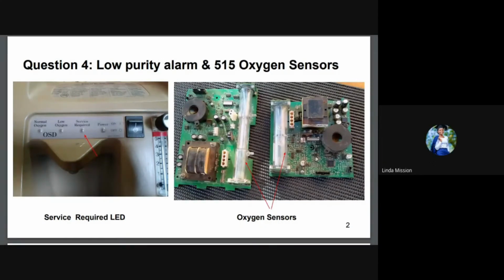Thank you, Maui. So the beeping audible alarm due to low oxygen purity gets activated when the concentrator is producing oxygen purity of less than 60%. Since you have replaced the sieve beds and serviced the compressor, and the purity is as required, then the problem is with the sensor. If you have another concentrator of the same model, try swapping around the concentrator control boards and see if the concentrator will work with the other board.